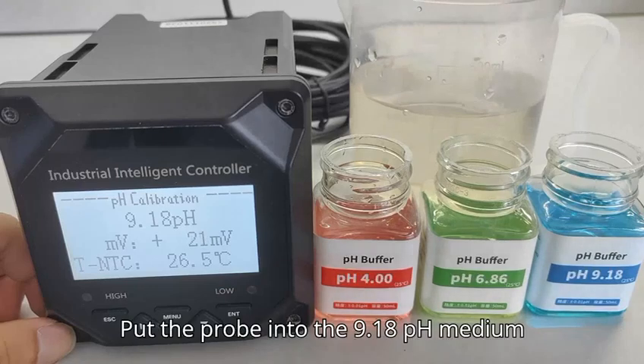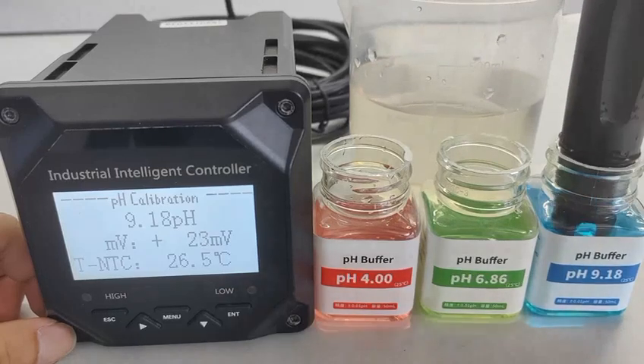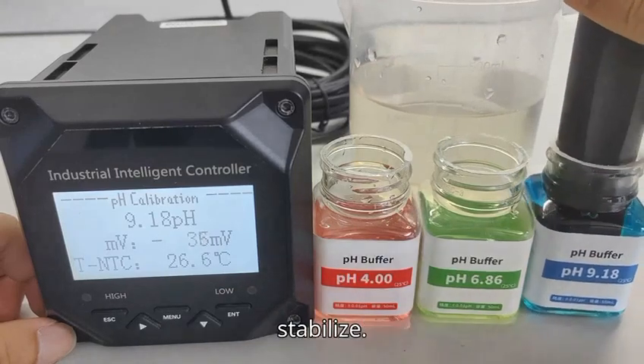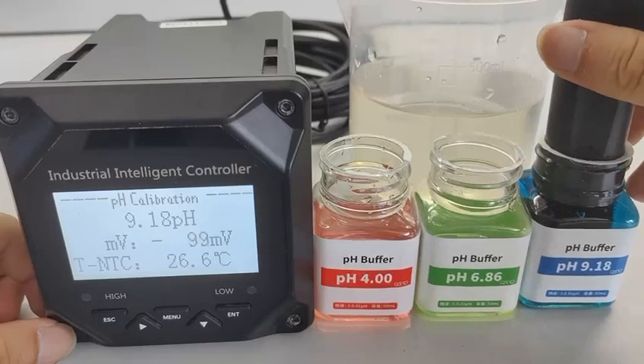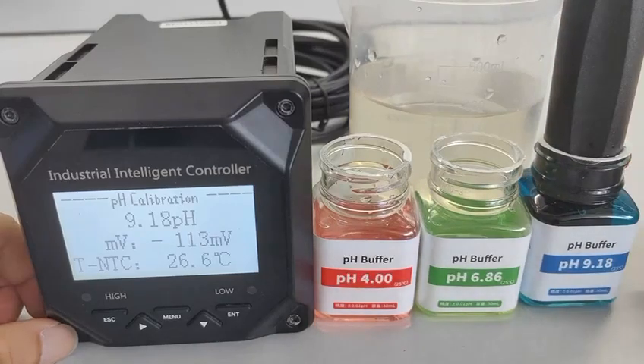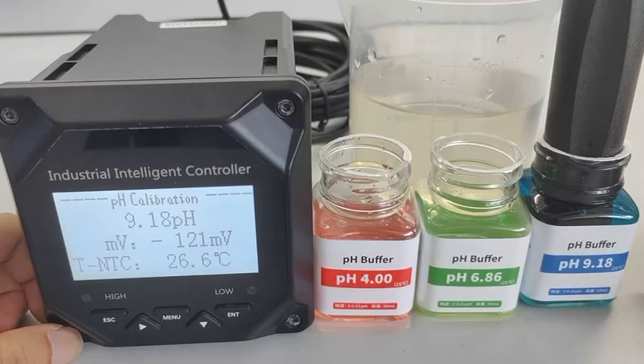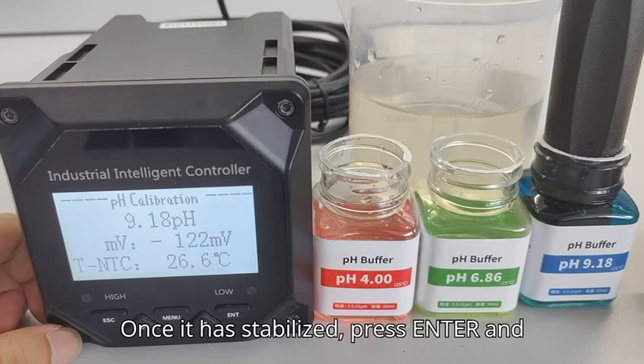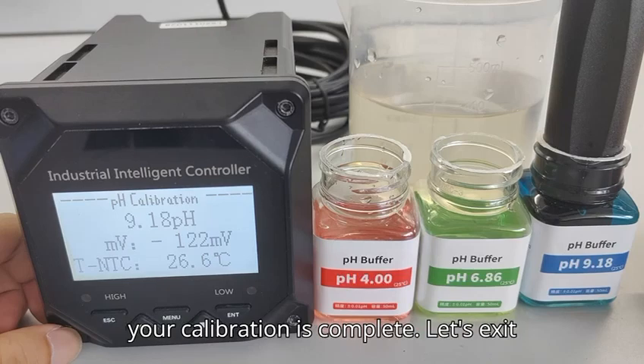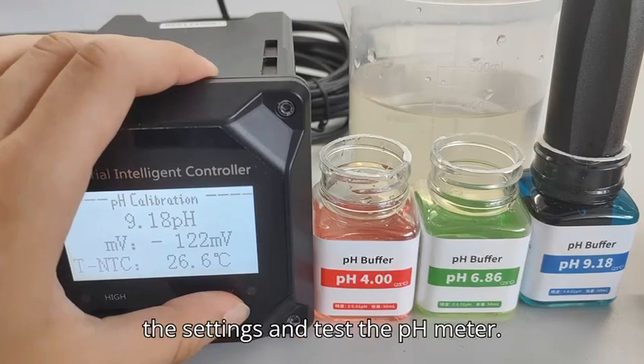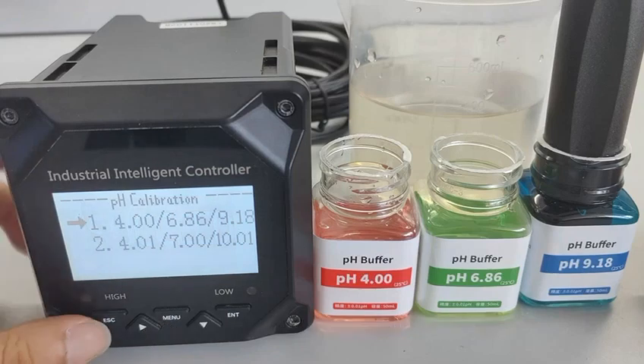Put the probe into the 9.18 pH medium and wait for the millivolt value to stabilize. Once it has stabilized, press enter and your calibration is complete. Let's exit the settings and test the pH meter.